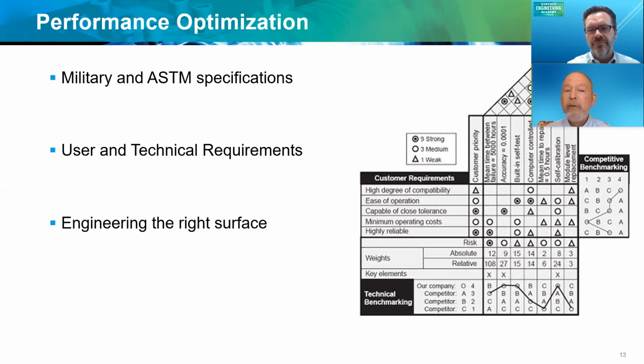specifications. And there's also the ASTM specifications, very similar in that they call out, for example, if you're going to do electroless nickel plating, the ASTM specification says if you have a surface exposure environment that's harsh, use this type of plating. It doesn't specify what harsh actually is. And then it says you should measure the coating by doing a salt spray test. And actually, that might not even be applicable to the medical device, especially if it's going to go through sterilization.